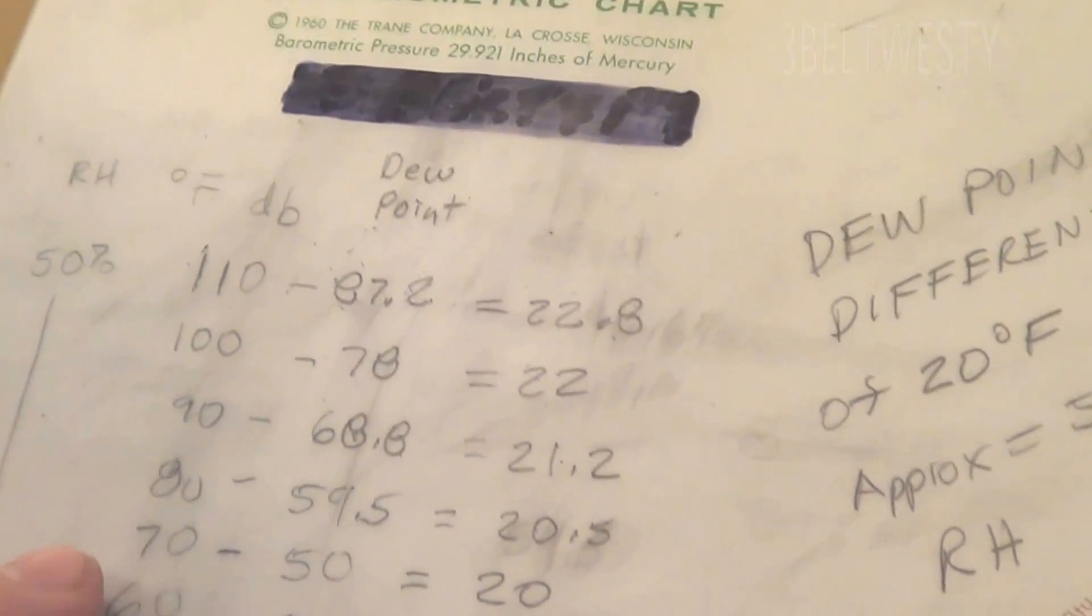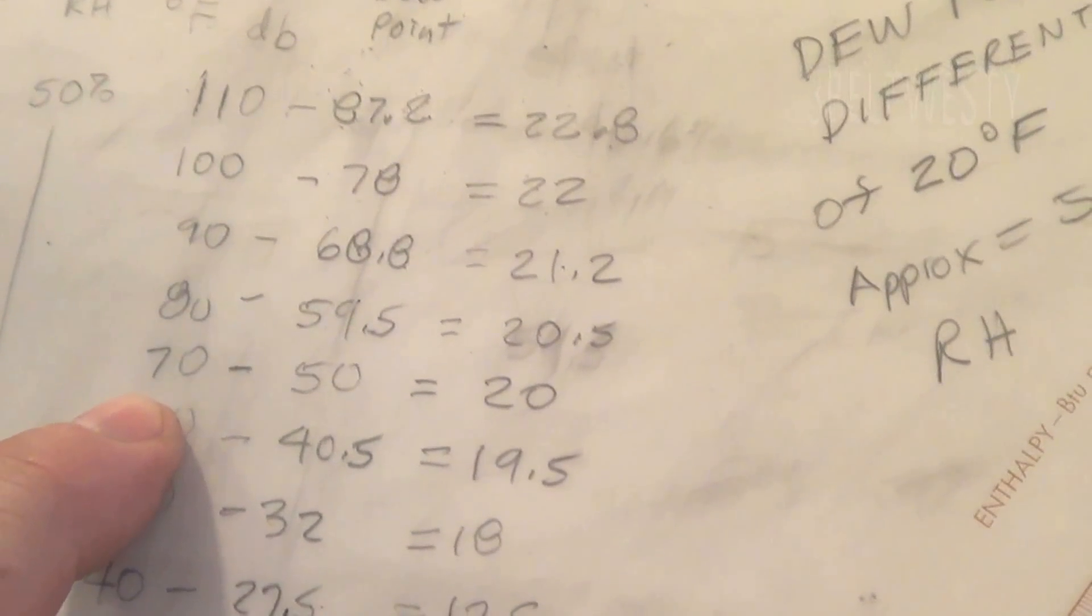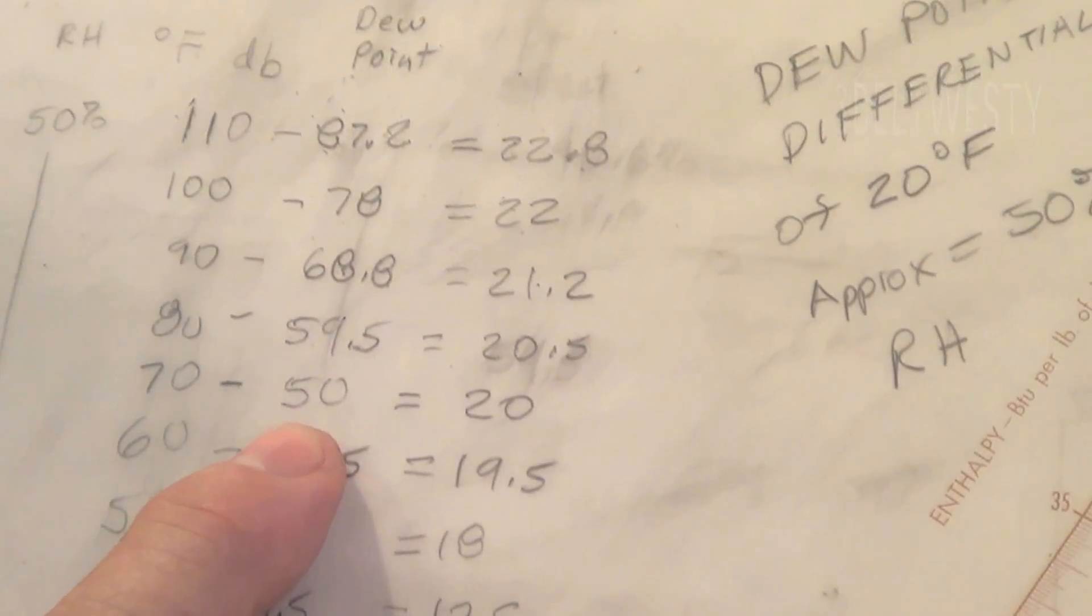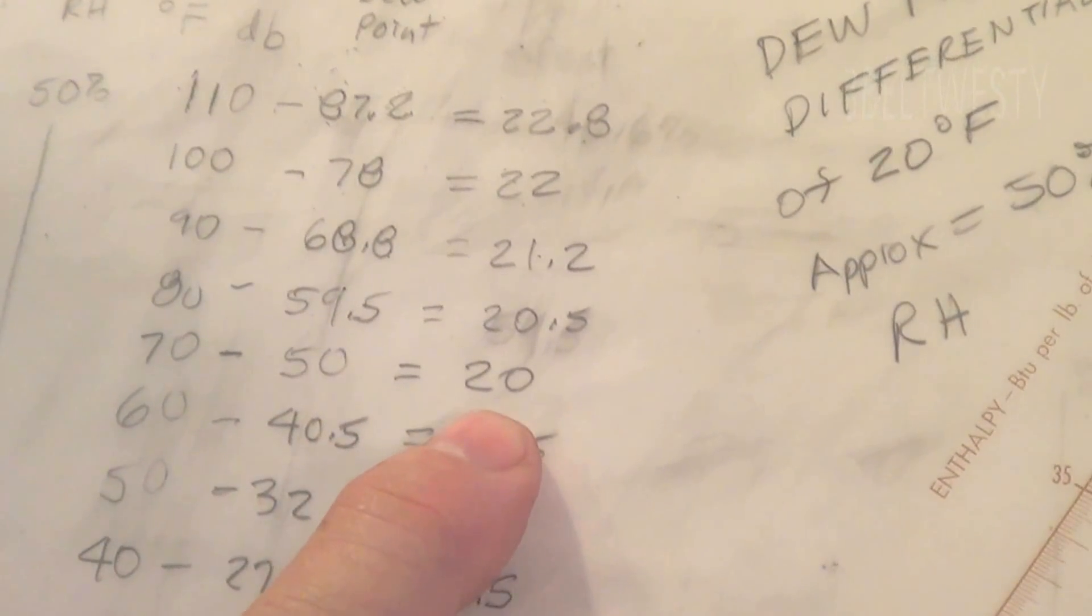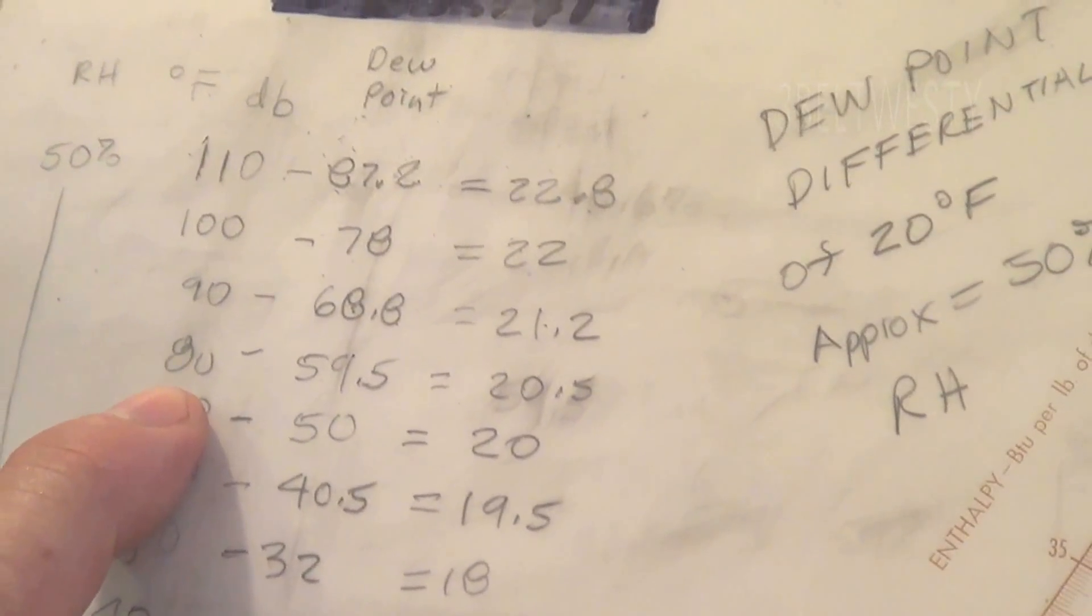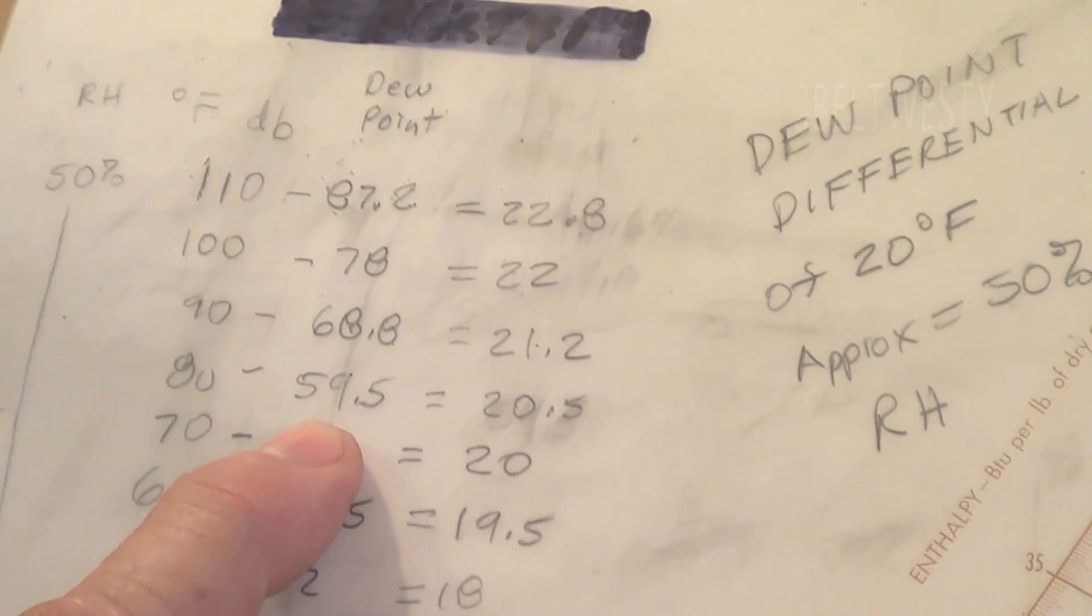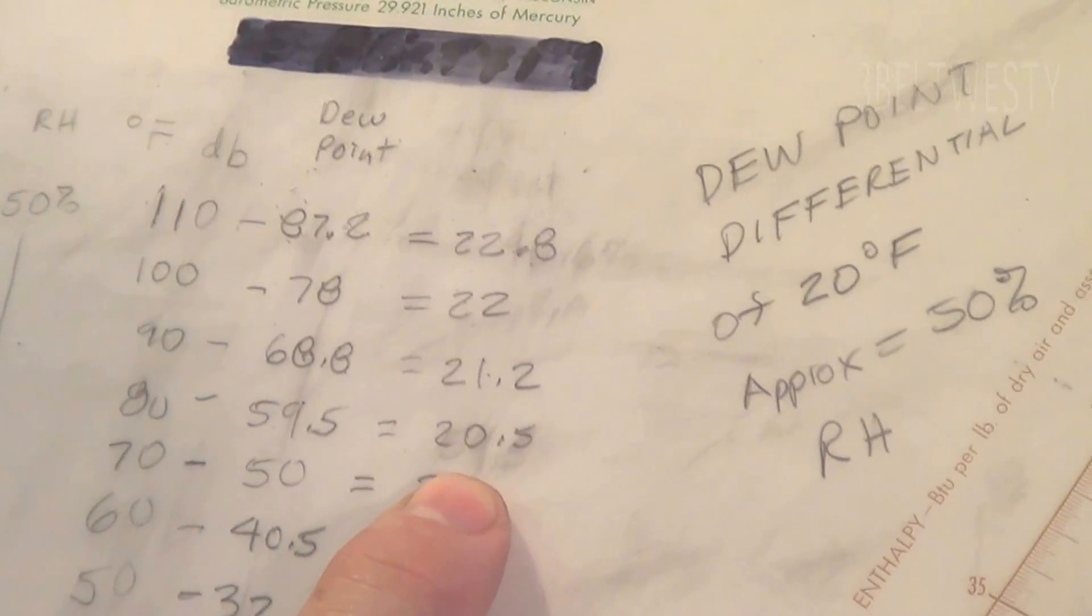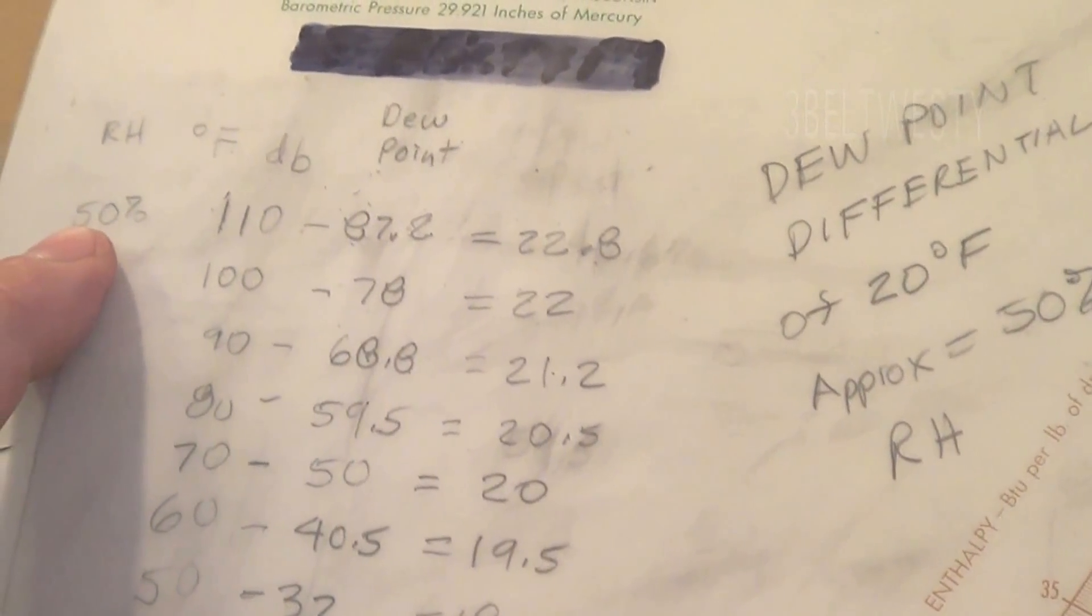Here's the actual error. Take a dry bulb of 70, dew point of 50, it's on the money at 20. You take 80 degrees, dew point of 59 and a half, get 20.5. This is at a 50% RH.